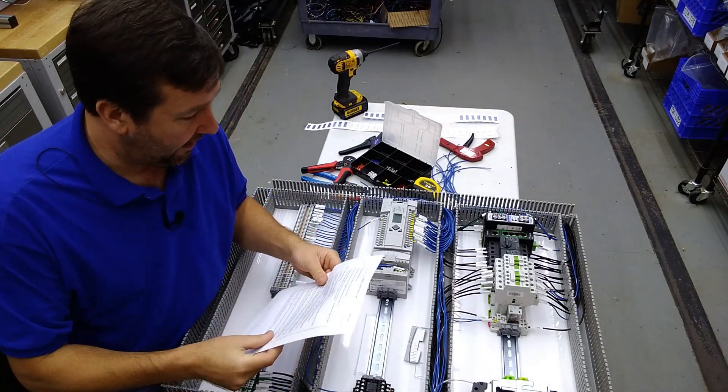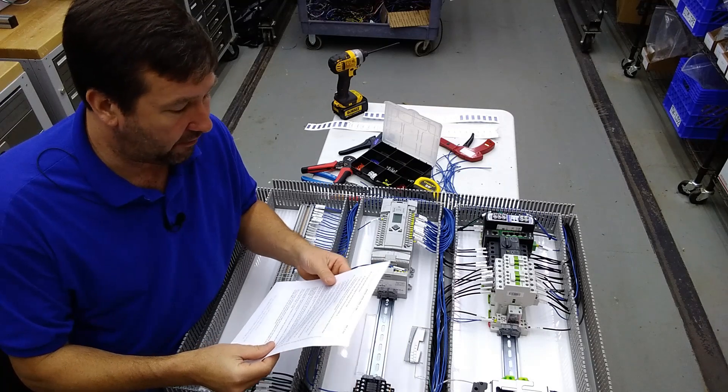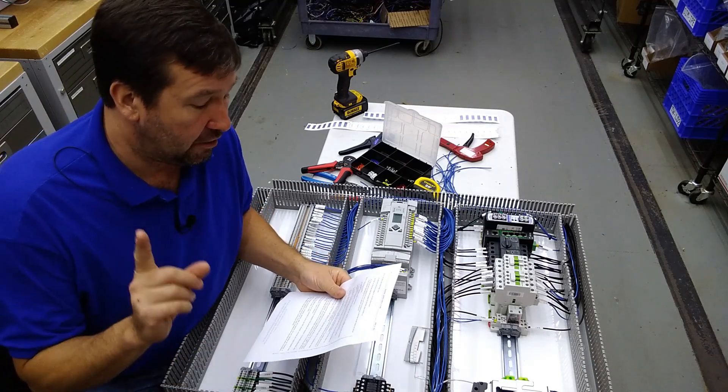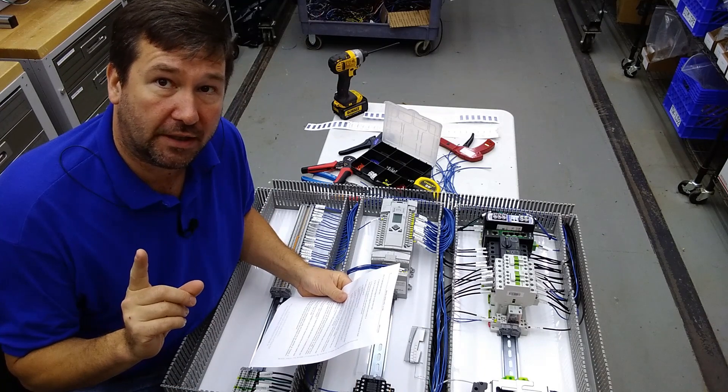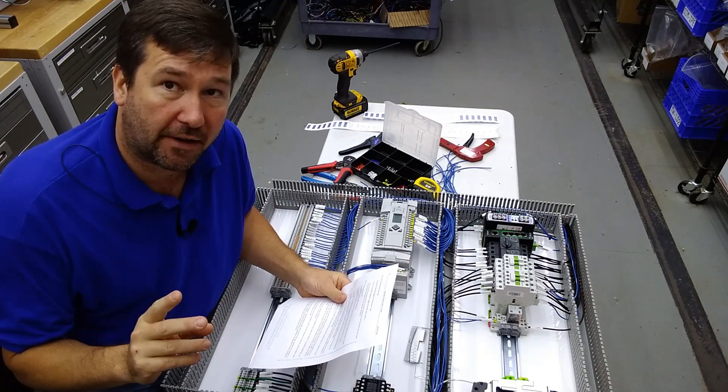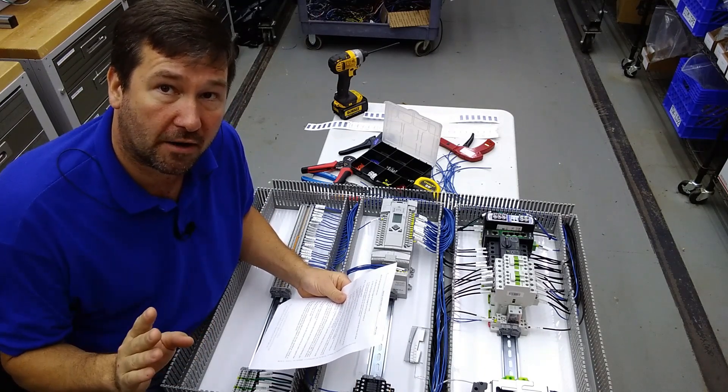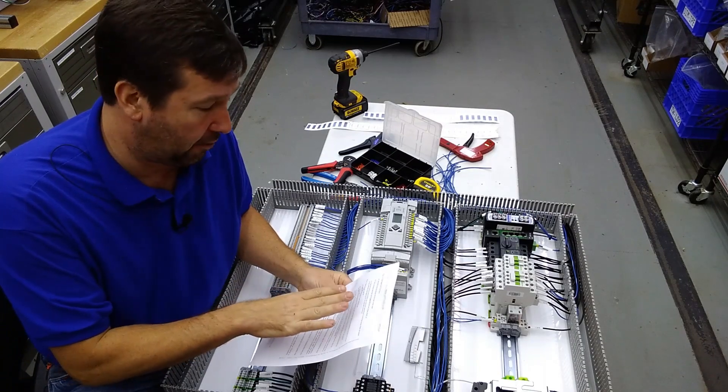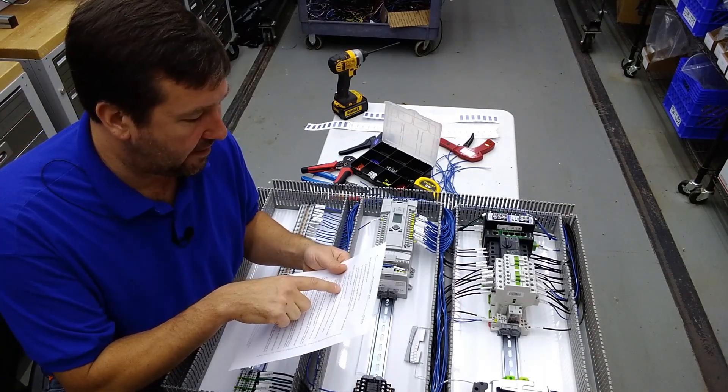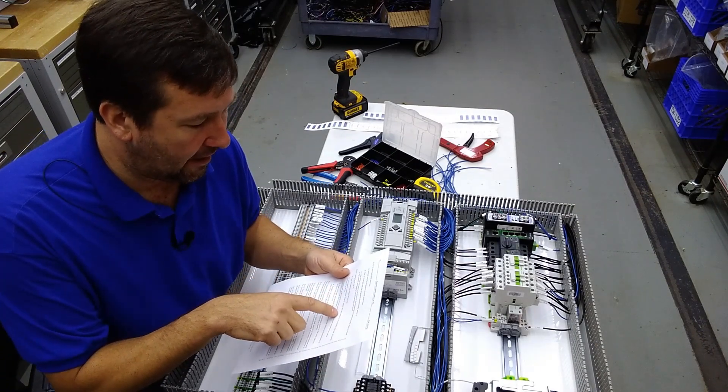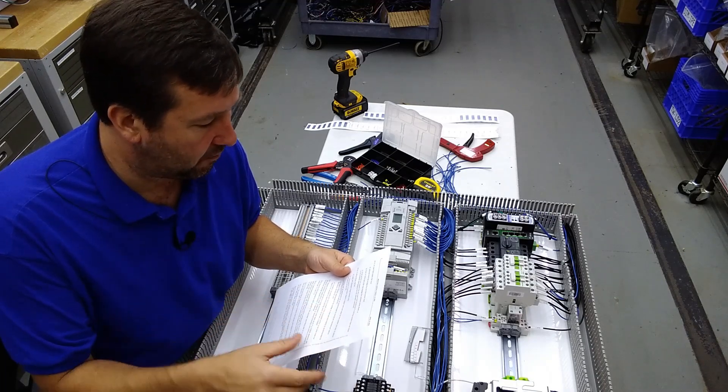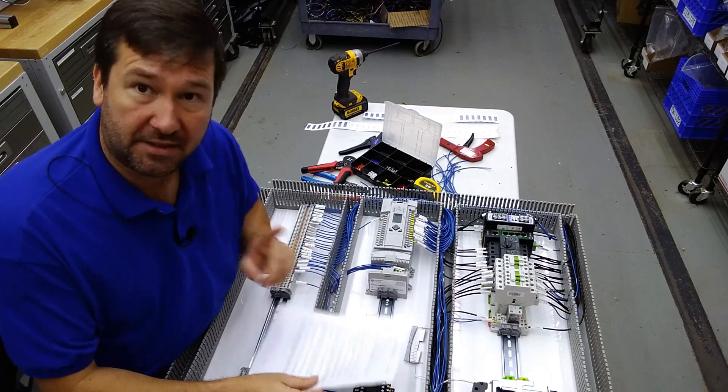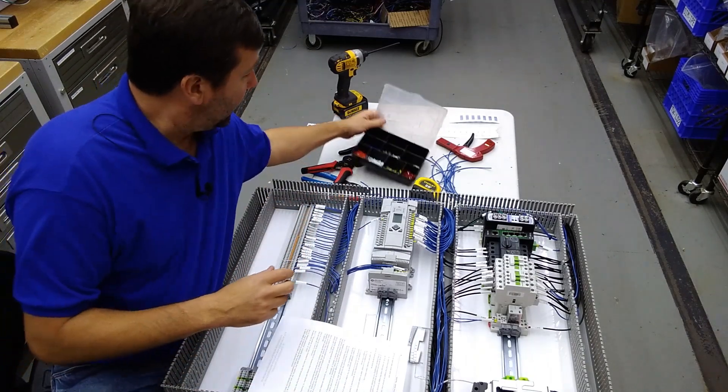And what that says is: a wiring ferrule shall be used with copper strand wires only. So you cannot use a ferrule with aluminum wire, at least according to UL 508A. Terminated in a connector rated for copper wire and rated for the number and size of wires crimped in the ferrule. Now this is kind of an interesting thing.